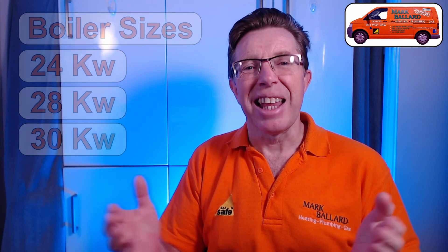These boilers come in three power ratings: you have the 24, the 28, and the 30 kilowatt boiler. When you try and decide what size boiler you need, the power of the boiler is a relation to how much hot water it produces, not your central heating. A typical house — say, three up and three down — only needs between 10 and 15 kilowatts of power, so there's plenty more power on top of that and that is purely for your hot water.